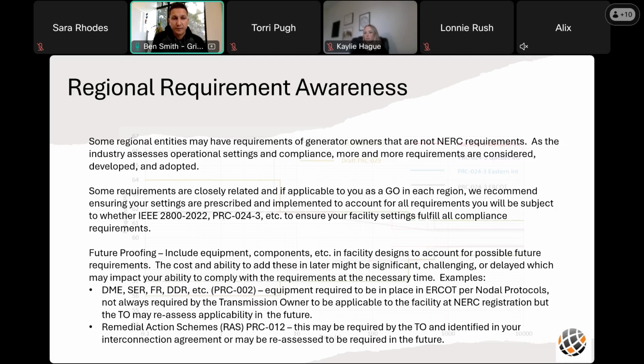Also a bit of future proofing recommendations. There's a couple reliability standards we look at for generator owners, PRC2 and PRC12. PRC2 is disturbance monitoring. It could refer to some of the requirements within that standard, or DME, SER, FR, DDR, all those acronyms related to fault recording and digital data recording. That's PRC2. We see that a fair amount as required in ERCOT from an equipment standpoint, but it doesn't necessarily mean the transmission owner is going to require that out of the gate for your facility to comply with. But they may out of the gate, they may in the future, and so the equipment needs to be in place. Similarly with remedial action schemes, or RAS, for PRC 12.